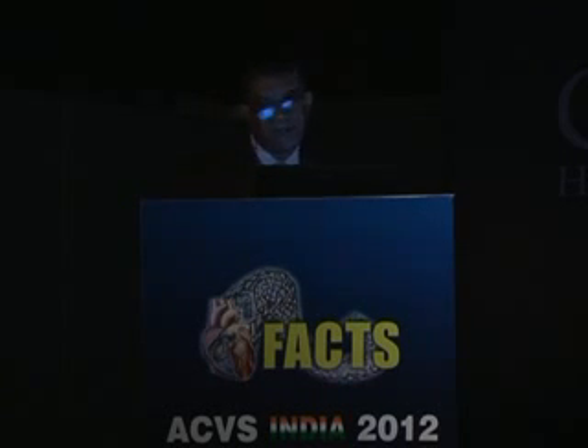Always check pressure transducers. We always want to have 2 pressure channels available with us during the procedure. This is a practice which has been completely given up in adult practice. Most of us are not concerned with 2 pressure channels, simultaneous pressure recordings, etc. Our own lab, which is dedicated to pediatrics, has 2 pressure transducers, but it's very important in the morning to check that they are functional.